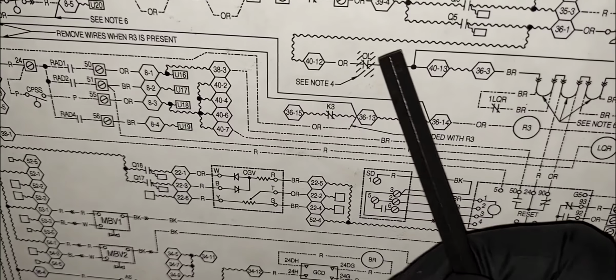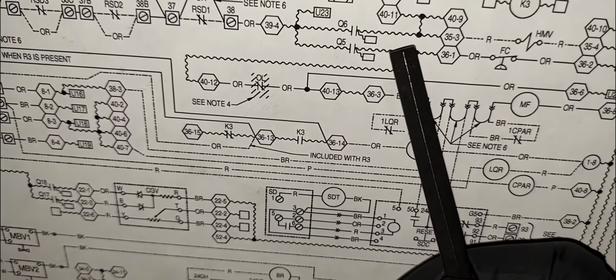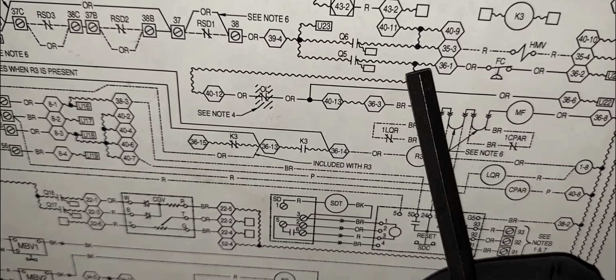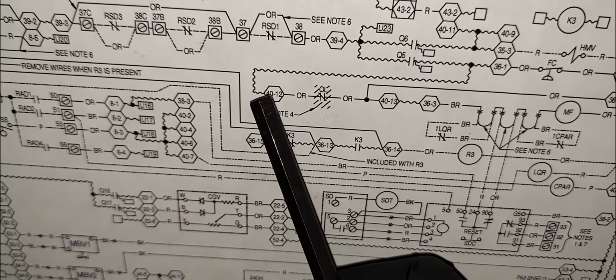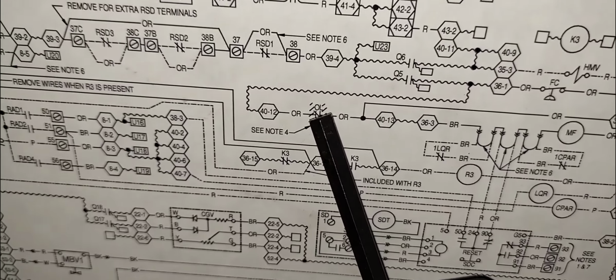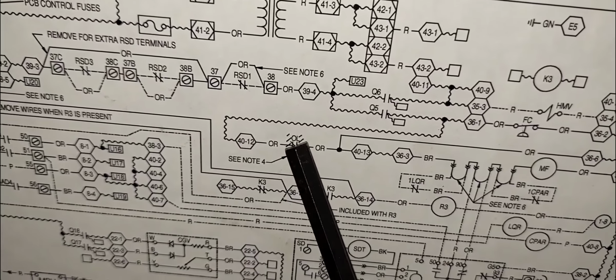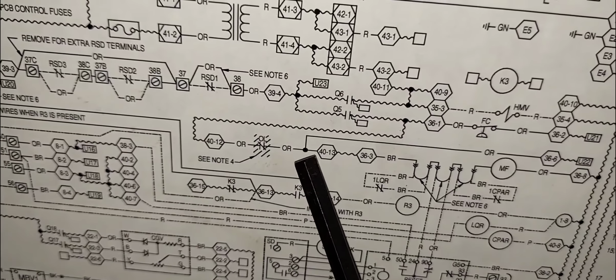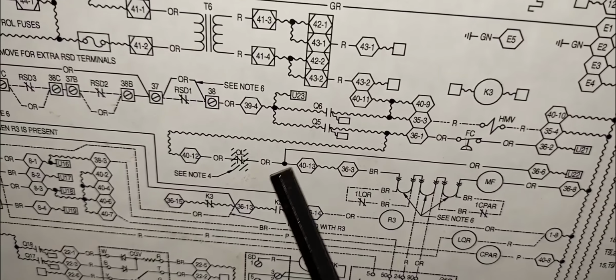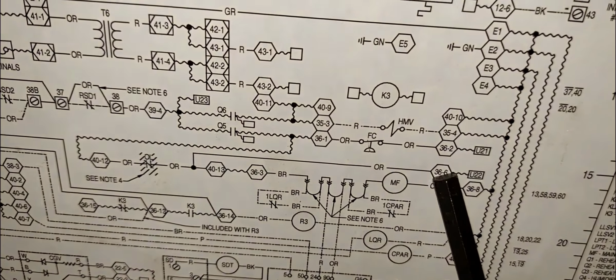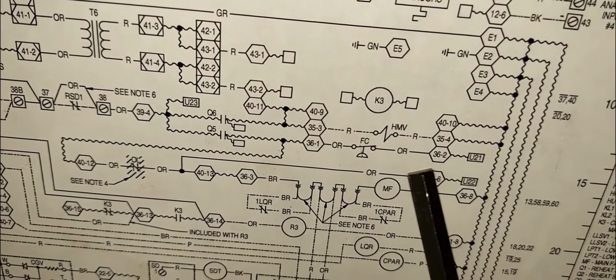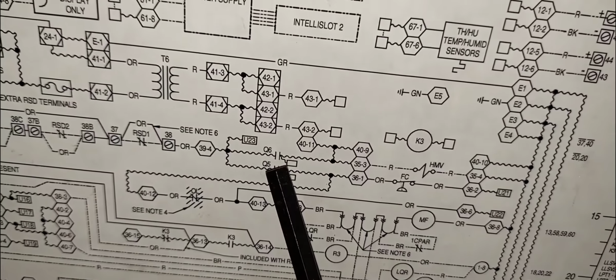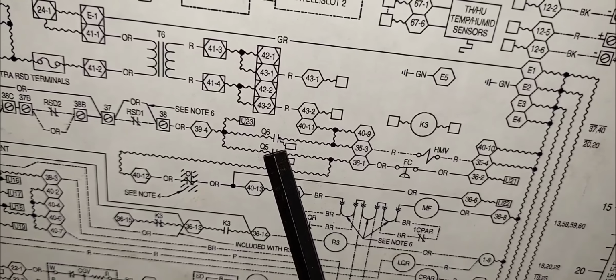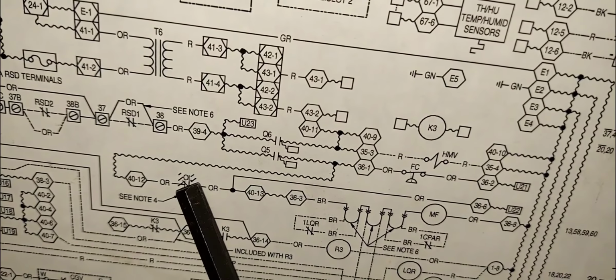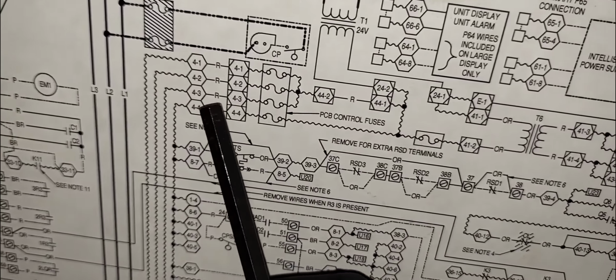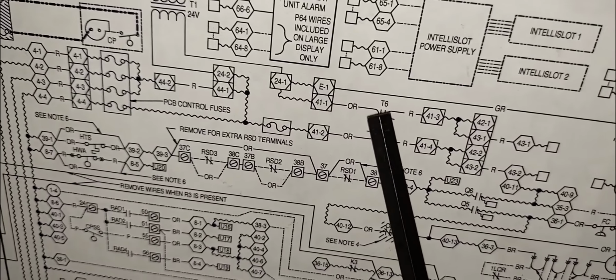So right here, we go back to Q5, so 24 volts leave the triac. Alright, and it immediately goes over here, and you can see there's an overload right here, main fan overload, which is currently what the alarm is saying. And so the 24 volts continues all the way, and it branches off right here and it goes here. Now here is where the alarm point is. If this terminal doesn't receive 24 volts while the main fan triac is closed, then it's going to generate an alarm for the main fan overload, because once again this line right here goes back into your fuse, this 24 volts, right, coming off of your transformer right here.